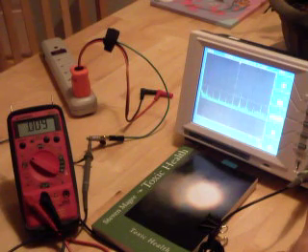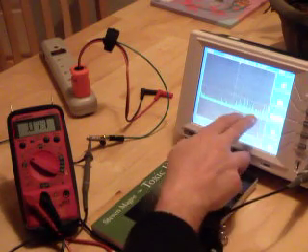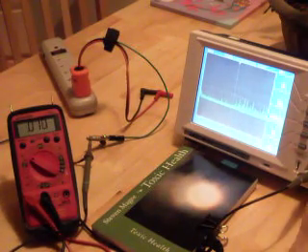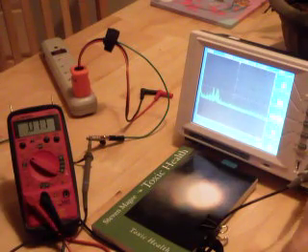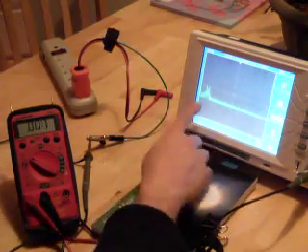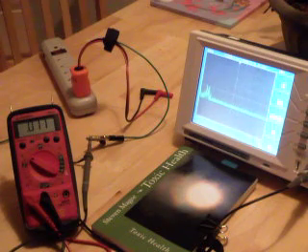I'm going to expand out a little more to see how extensive these harmonics are. Now at 100 kHz per division, we can see something from 500 kHz upward also on the system. Moving to 1 MHz per division, we can see that right around 1 MHz there is a spike in frequencies coming from the grounding system — something generating frequencies in the range of 0 to almost 2 MHz at this house.